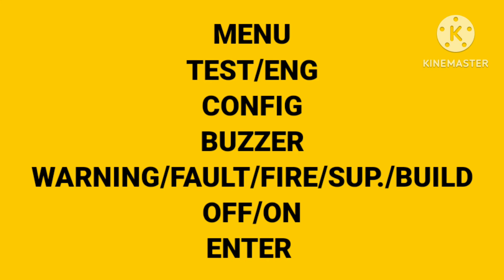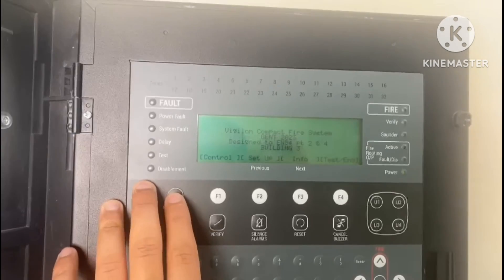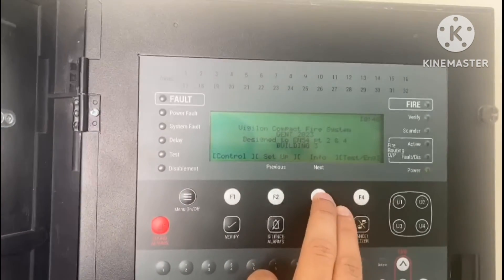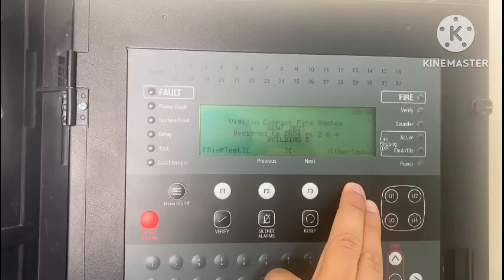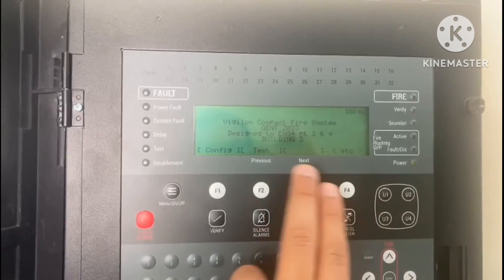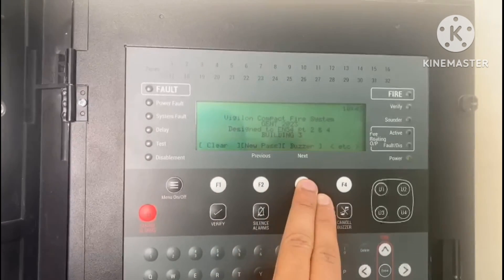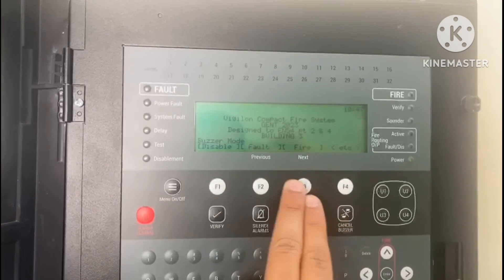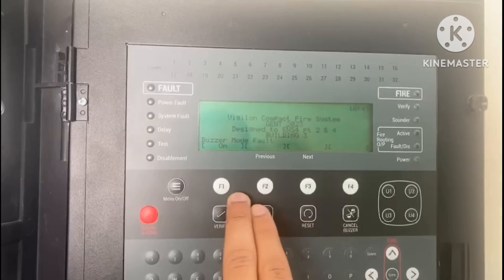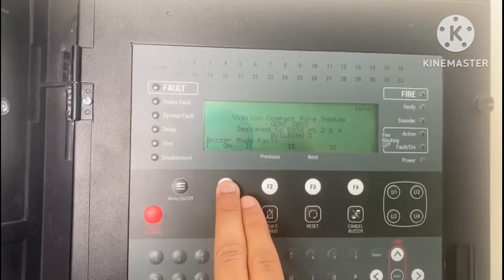Now we'll show it in the video. Go to Menu, then Test, Engineering, then Config F1, then Buzzer. You will see the option Fault, then On or Off. This is how you can turn the buzzer on and off for different alert types.